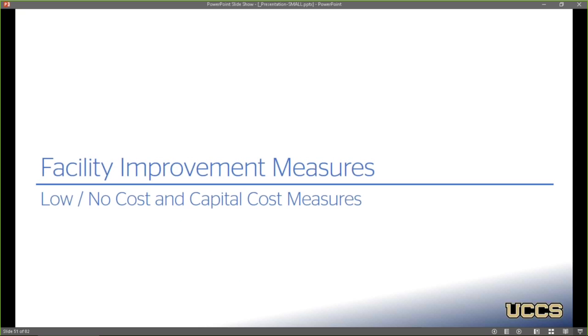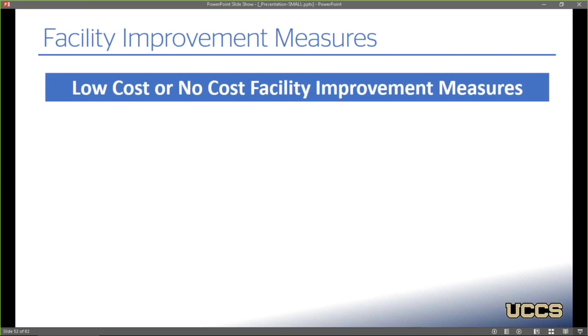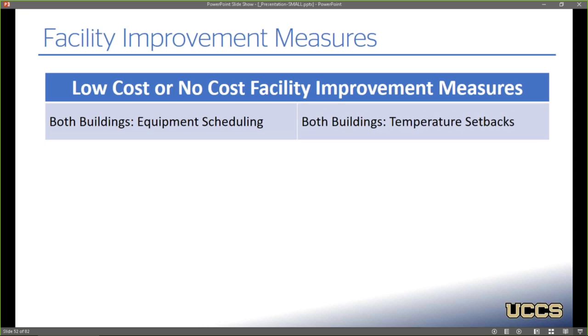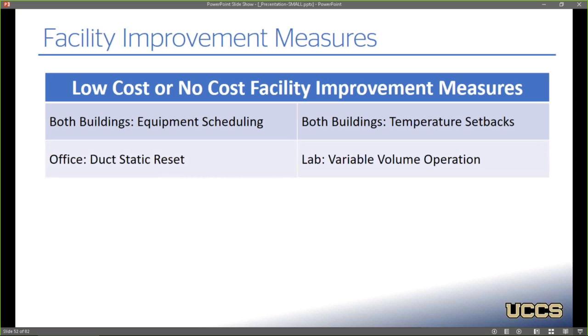So moving on to the facility improvement measures. So the low cost or no cost measures, these aren't necessarily quantified. These should be done at an absolute minimum. So they should re-implement some equipment scheduling as well as temperature setbacks, and they don't have to get super aggressive with it, but something is better than nothing. They can look at re-implementing that duct static reset. They can turn that lab unit into a kind of crude VAV system. They already have the VFD on the unit, and they're not really using it as a lab very often.